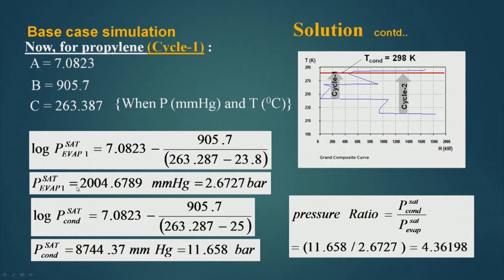For the evaporator the pressure is 2.6727 bar, and for the condenser using the same equation it comes out to be 11.568 bar — or more precisely 11.658 bar. That means the pressure has to be raised from 2.6727 bar to 11.658 bar through compression. So the pressure ratio becomes 11.658 divided by 2.6727, which comes out to be 4.36198. This is the pressure ratio for cycle 1.